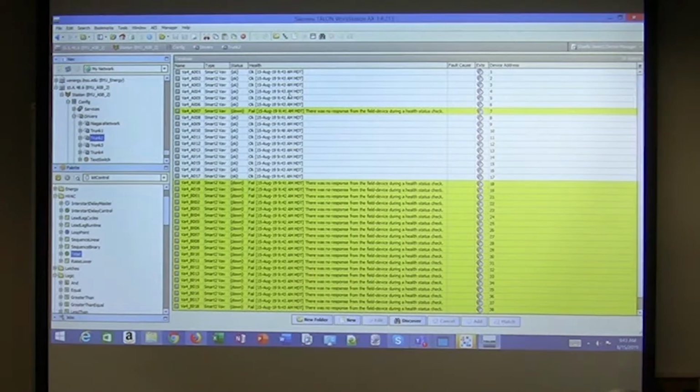It's got pretty colors on it. Is that a good thing or a bad thing? A bad thing, right? If it's yellow, it's mellow. So yellow tells us that he's not responding back to any requests. The JACE can't find that device, okay?